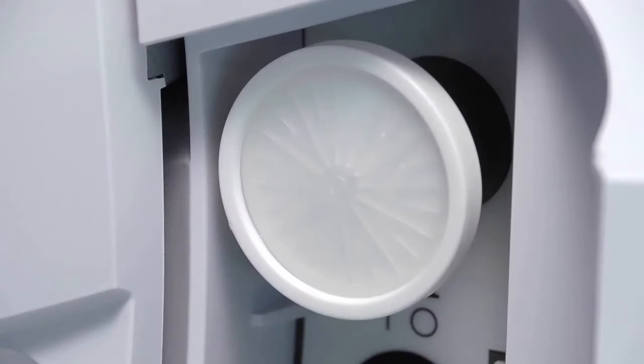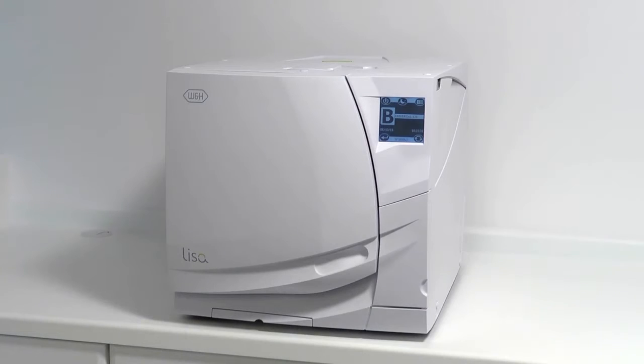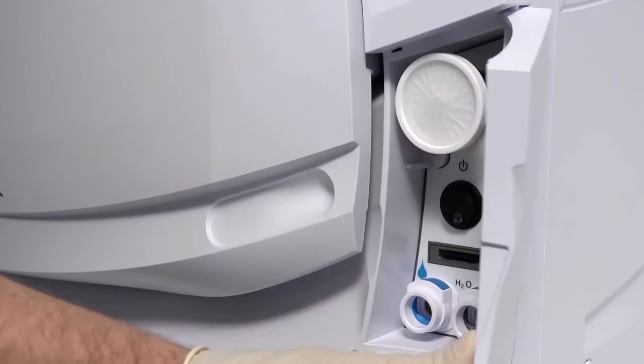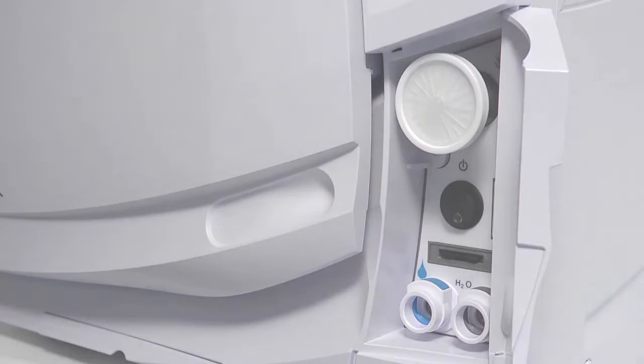The bacteriological filter is an essential component of your W&H Lisa sterilizer. It filters the air entering the chamber when drying the load, ensuring the air does not become recontaminated. The filter can be found behind the service door.